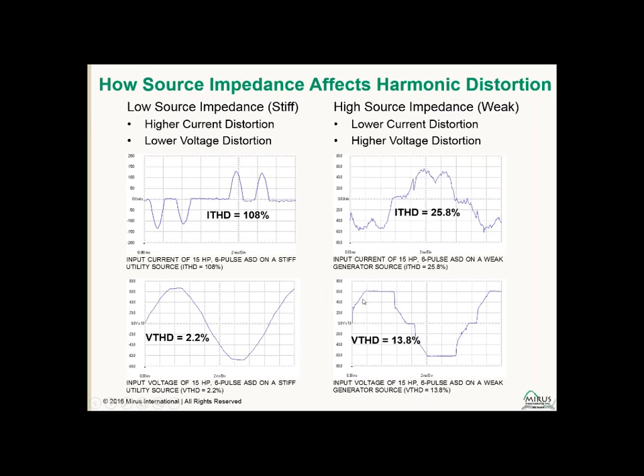You can see very severe flat topping and other distortions on the voltage, and that's a result of the remaining harmonic currents, even though they're much lower than on a stiff source. Even the 26% of current distortion now creates almost 14% of voltage distortion.